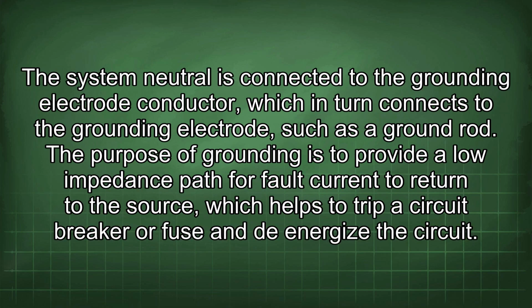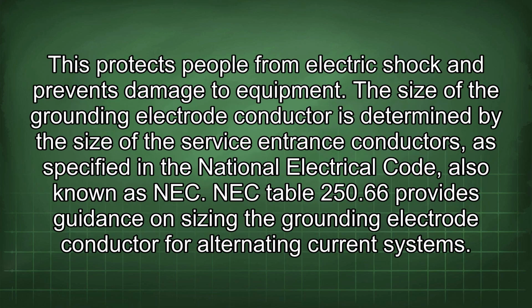The system neutral is connected to the grounding electrode conductor, which in turn connects to the grounding electrode, such as a ground rod. The purpose of grounding is to provide a low impedance path for fault current to return to the source, which helps to trip a circuit breaker or fuse and de-energize the circuit. This protects people from electric shock and prevents damage to equipment. The size of the grounding electrode conductor is determined by the size of the service entrance conductors, as specified in the National Electrical Code, also known as NEC. NEC Table 250.66 provides guidance on sizing the grounding electrode conductor for alternating current systems.